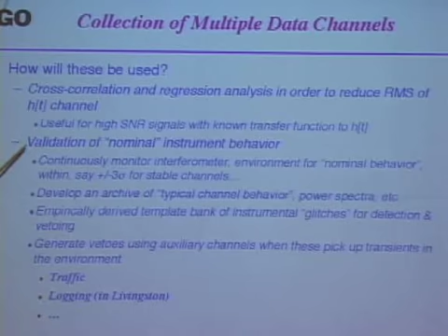The other purpose of the multiple channels is to validate that if we see something in the h(t) channel, the instrument was behaving nominally. So we want to continuously monitor the interferometer environment and make sure that all these signals are within nominal, let's say plus or minus 3 sigma performance. The other thing we can do is, empirically, determine what a typical channel's power spectrum looks like, so that we can compare the data at this epoch with historical trends to identify whether we have any outliers in the behavior of the instrument.